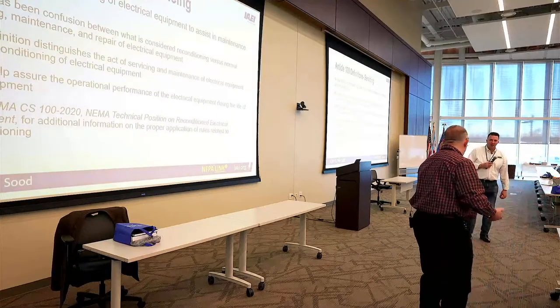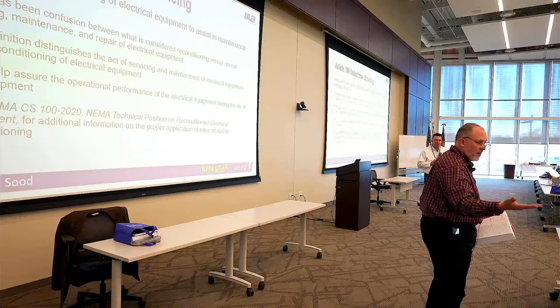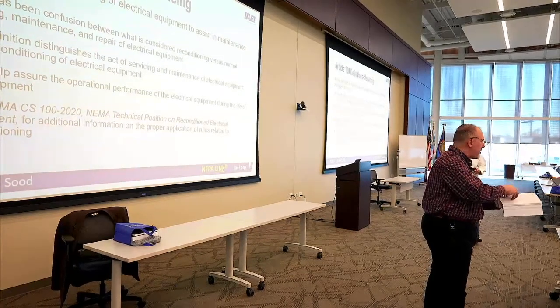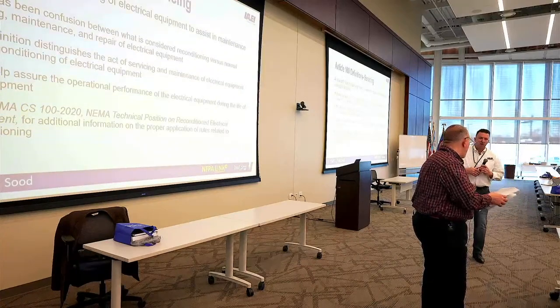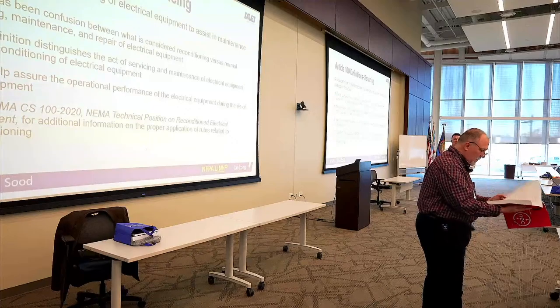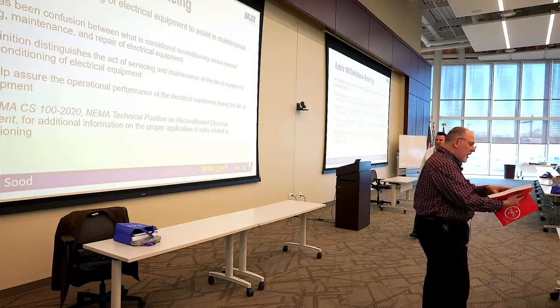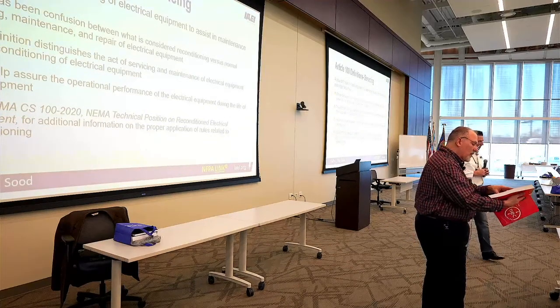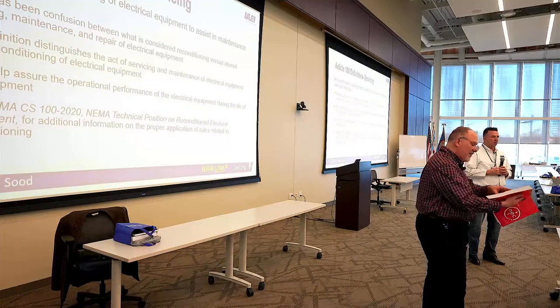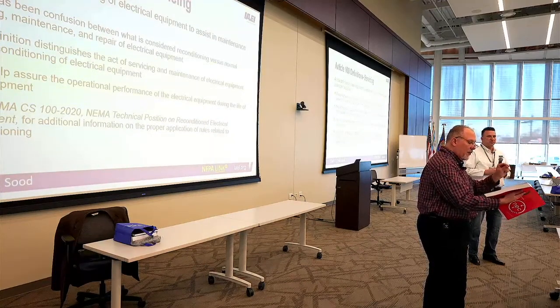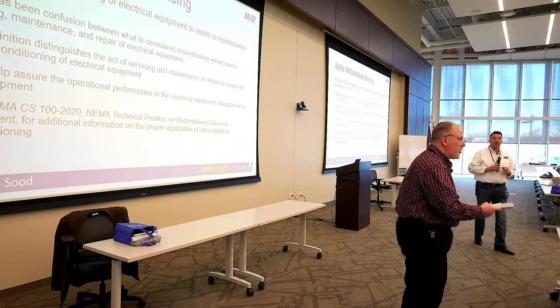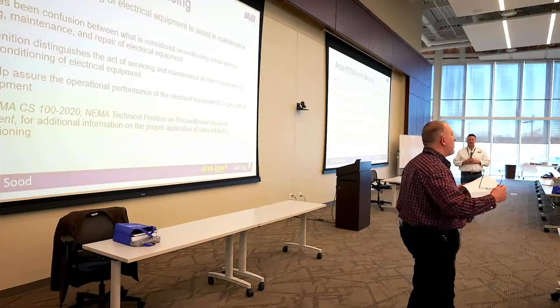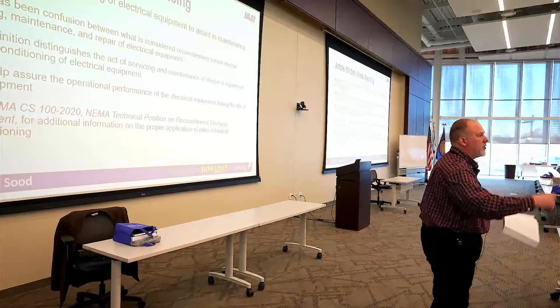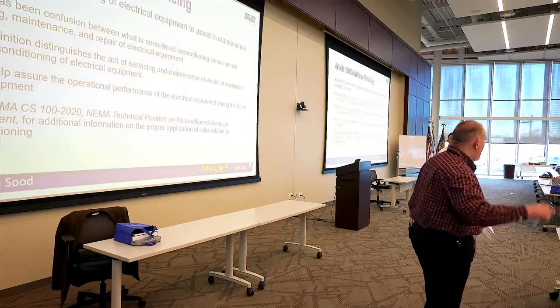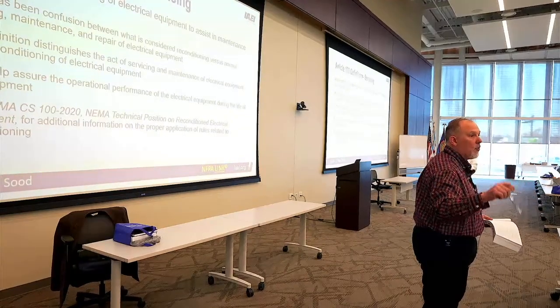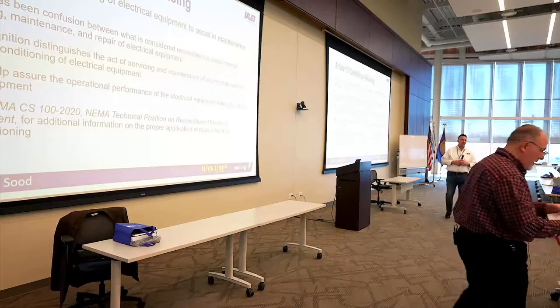So I replace a breaker, or to your point, that little brick of relay inside of a transfer switch. If I'm following manufacturer's instructions and replacing it, I don't meet the definition of recondition. So then the next question was, well, if I'm servicing it, then what does that mean, and what are the requirements around servicing? Servicing is the process of following a manufacturer's set of instructions or applicable industry standards to analyze, adjust, or perform prescribed actions upon equipment with the intention to preserve or restore the operational performance of the equipment. So servicing can include maintenance, and NFPA 70B covers the maintenance. If I'm doing maintenance on a motor, lubricating it, doing all these things to get it working, I'm not reconditioning it, I am servicing it. So now I'm following the requirements in 110 for servicing, not the requirements for reconditioning.